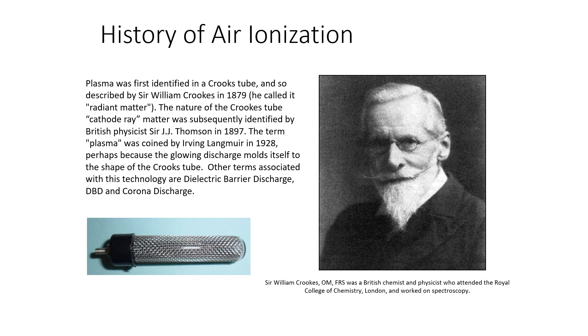In the photo here, you can see an example of what the plasma tube looked like — what we call corona discharge or dielectric barrier discharge. Those are the two terms in the market for this technology. It's more correct to say corona discharge or dielectric barrier discharge. The reason it's called dielectric is that the glass — or it could be mica, a ceramic, or a composite type tube — acts as the dielectric. You have to have a dielectric, a filament on the inside, and one on the outside which is grounded. When you have that, you have corona discharge.